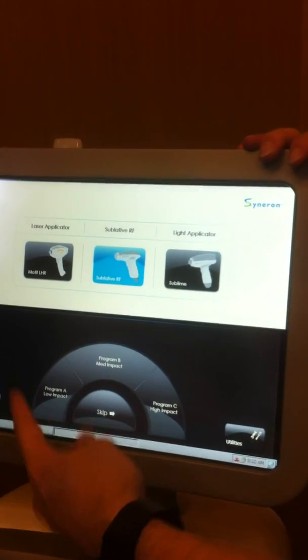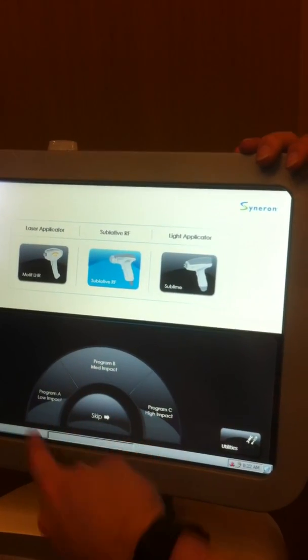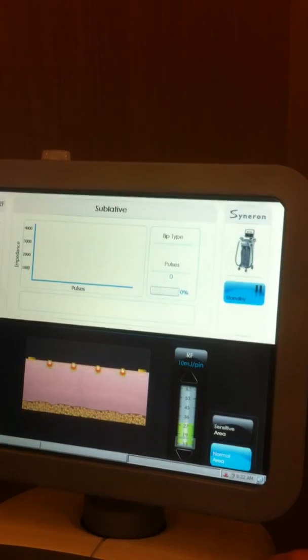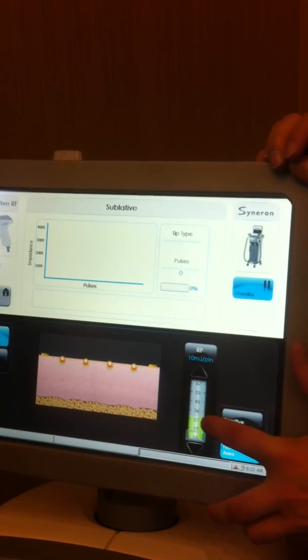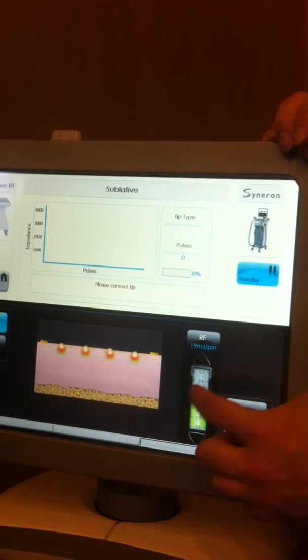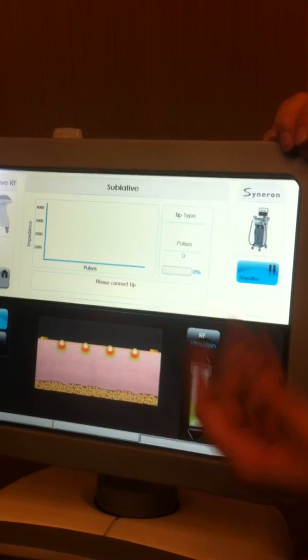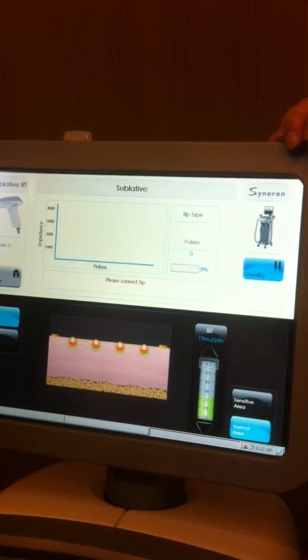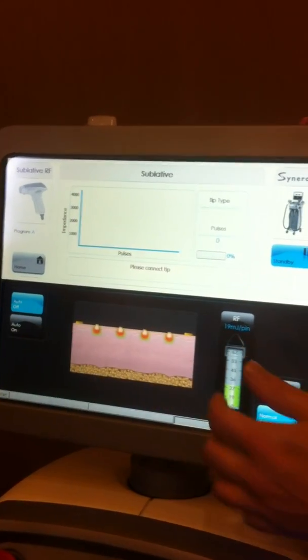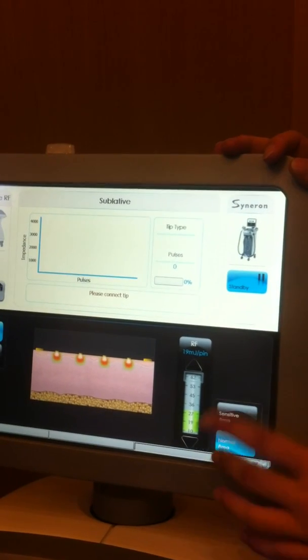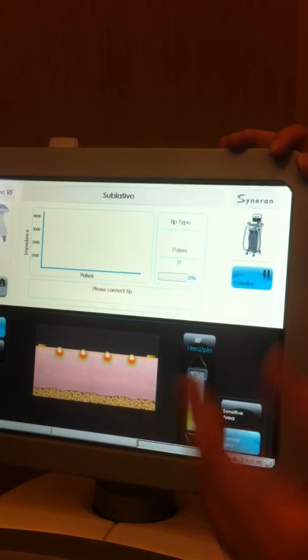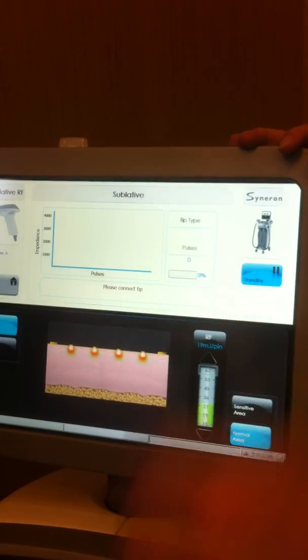So we'll go home. We can select the other one. If we select sublative, you get your familiar speed dial A, B and C. When you click on the program, it highlights here just like the other programs do and you can go to the full energy scale. I go up to 62. I see that my graphic changes, have auto on, auto off, and then normal and sensitive just like I have in the other one.